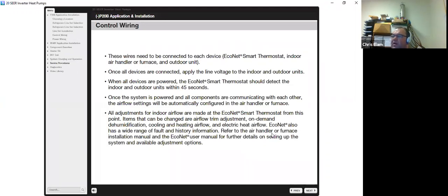You can refer to the air handler or furnace installation manual for further details on setting up the equipment and the adjustment options. If you're using the EcoNet thermostat with the air handler or the gas furnace, your dip switches do not come into play at that point. At that point, all your adjustments and all your controls are controlled from the EcoNet.